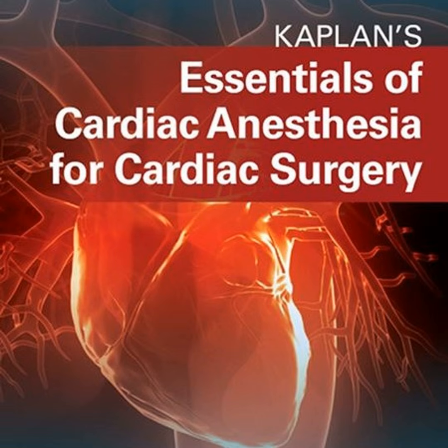Right. And the ICD's primary function is to continuously monitor the cardiac grid for chaotic, high-rate electrical activity, which it interprets as ventricular fibrillation, imminent death. And the high-frequency noise from a surgeon's electrocautery tool mimics that exact electrical signature. Precisely. If the ICD misinterprets the surgical cautery as a lethal arrhythmia, it will instantly deliver a massive 800-volt countershock directly into the patient's myocardium while they're lying open on the operating table. Which is horrifying. So to prevent the patient from being electrocuted by their own pacemaker, the anesthesia team has to execute strict mitigation protocols. Very strict.